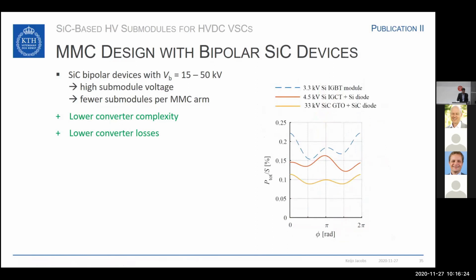And this means a difference for the converter losses. We have simulated that and compared a conventional solution of a 3.3 kV silicon IGBT module, a silicon IGCT, and the 33 kV silicon carbide GTO. And as you can see, for the silicon carbide GTO, we get reduced converter losses. Regardless of the angle, all the time, these losses are lower than with the comparison cases.